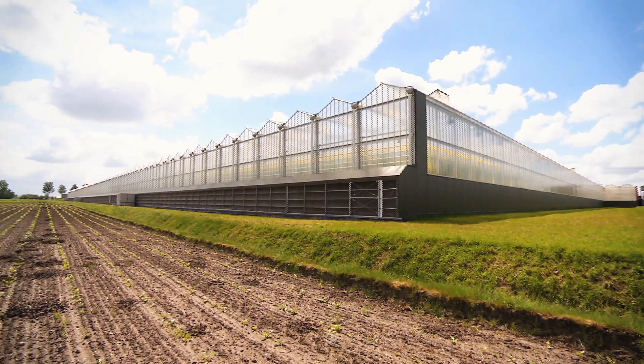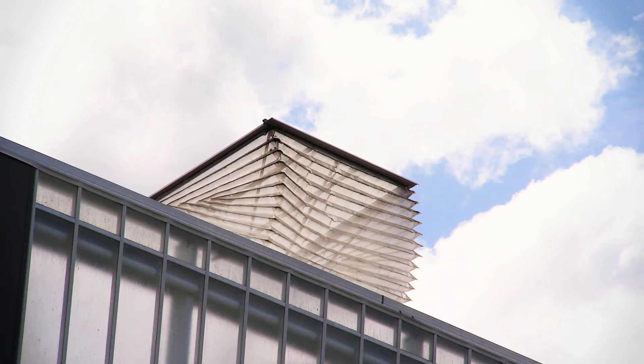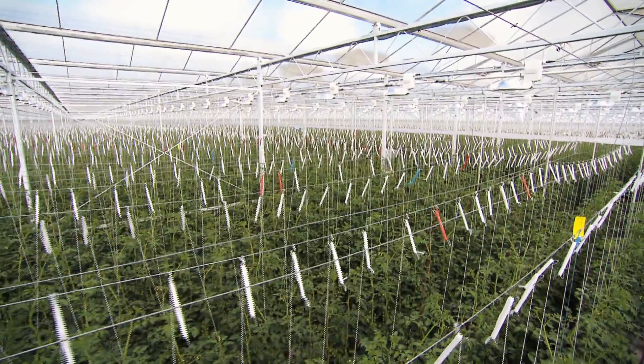To limit the presence of insects, the number of ventilation windows is limited to only 750 on 9 hectares, all equipped with insect nettings. In the greenhouse there is a positive pressure of 10 Pascal, which pushes the warm air through the screen during the night, so the blackout screen can remain closed and light emission remains at a minimum.